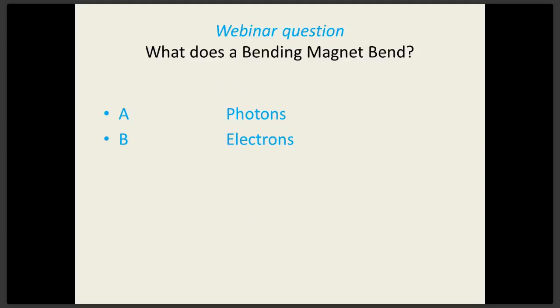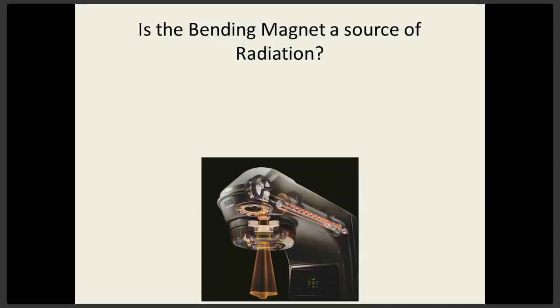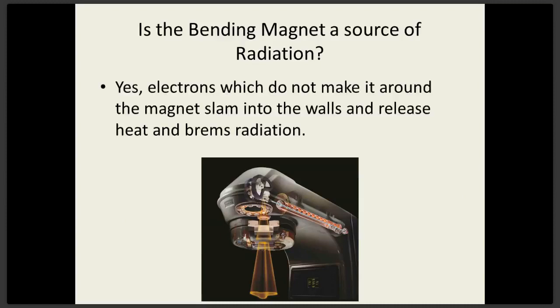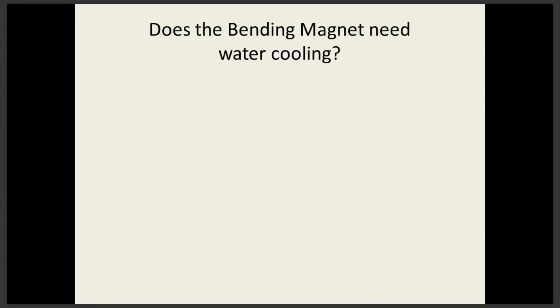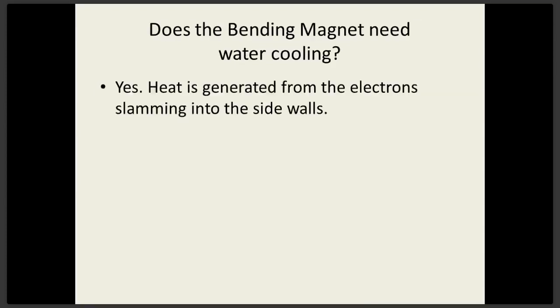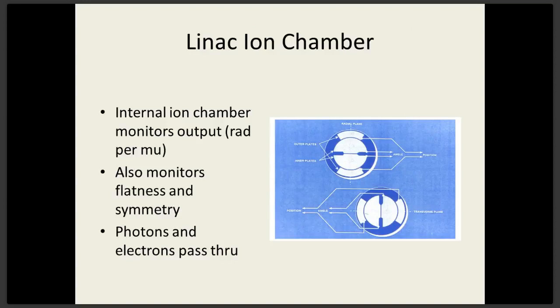Answer is electrons. You can't bend photons. Photons are not charged, and they generally don't react to magnetic fields unless it's something the size of a star. So it won't happen in a linear accelerator. We don't bend photons. Is the bending magnet a source of radiation? Absolutely. Electrons that don't make it around the magnet slam into the walls and release heat and Bremsstrahlung radiation. That's why that bending magnet is heavily, heavily shielded. Does the bending magnet need water cooling? Absolutely, because of the heat generated from the electrons slamming into the walls, the bending magnet has to be cooled.